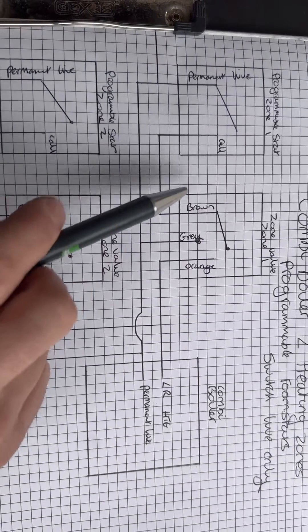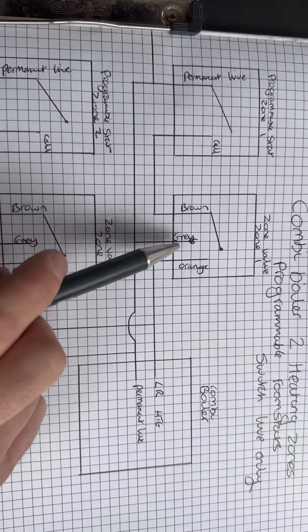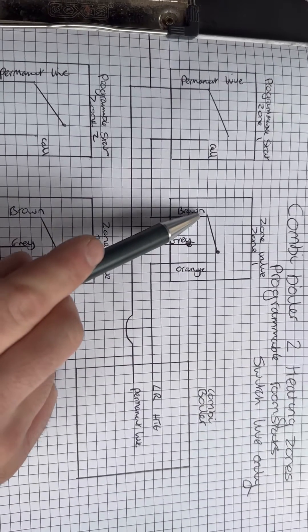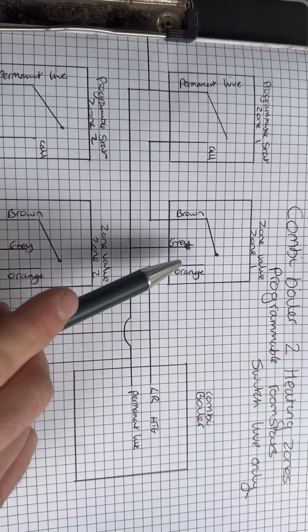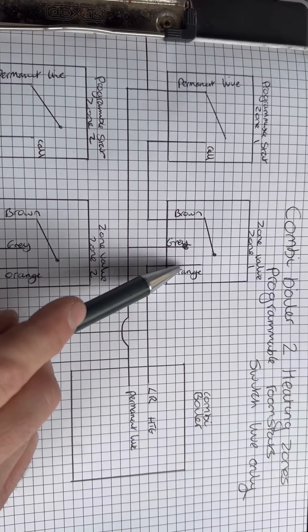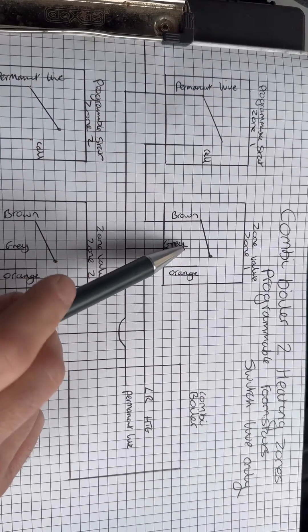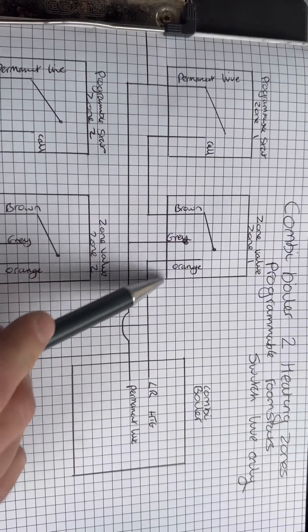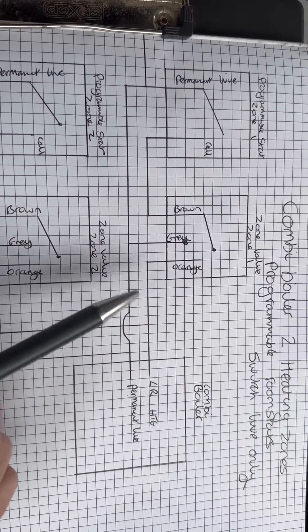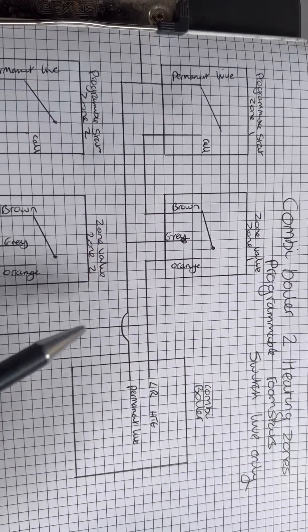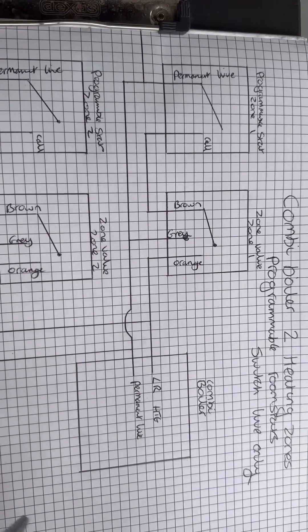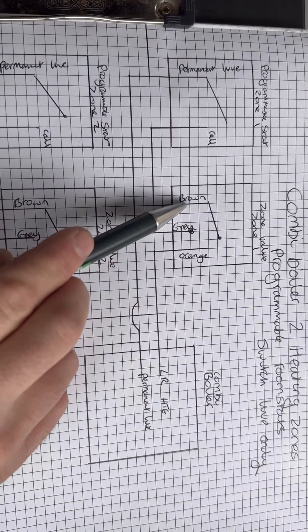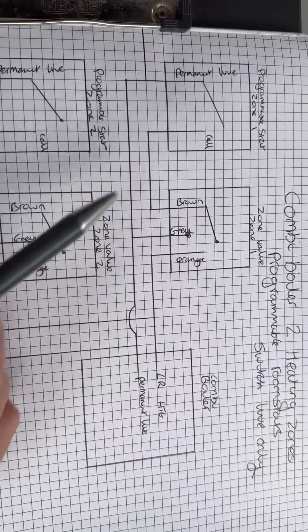So I went up to the airing cupboard, whipped out the multimeter, checked on brown - was I getting 240 on brown? I wasn't, but I was getting 240 on orange. So what was happening was the head had stuck, so permanent gray was linked over to orange, firing the boiler constantly. So in that instance I had to change the whole valve.